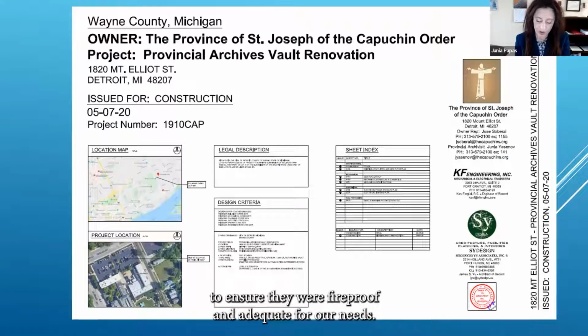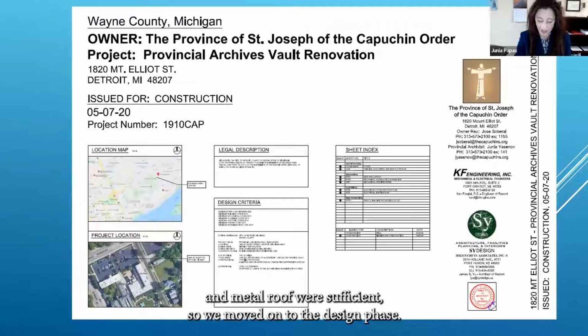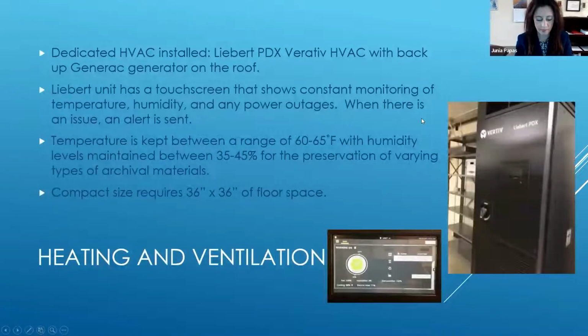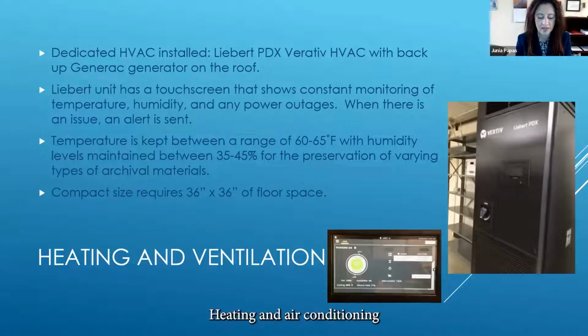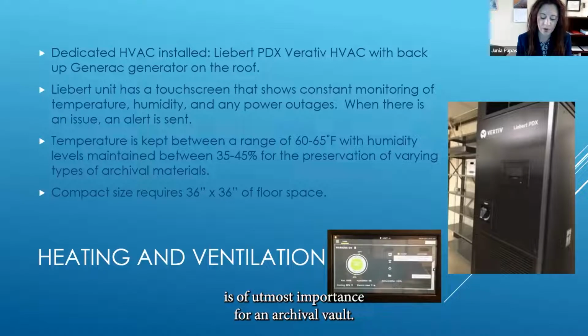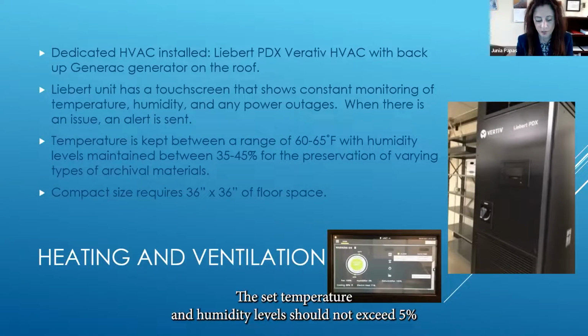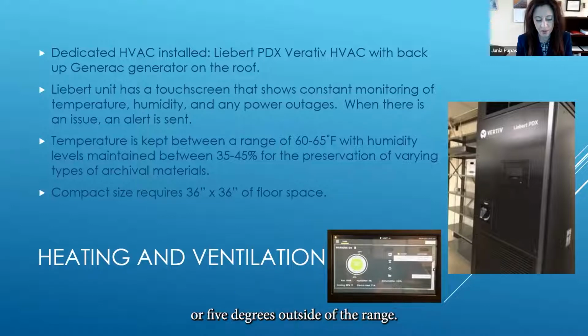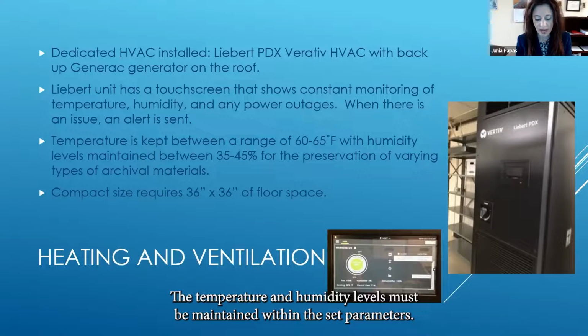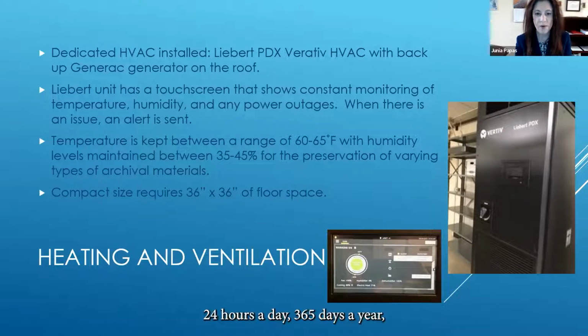After this, the walls and roof were spec'd to ensure they were fireproof and adequate for our needs. The construction engineers deemed the cinder block walls and metal roof were sufficient, so we moved on to the design phase from there. Heating and air conditioning is of utmost importance for an archival vault. The set temperature and humidity levels should not exceed 5% or 5 degrees outside of the range. The temperature and humidity levels must be maintained within the set parameters 24 hours a day, 365 days a year.